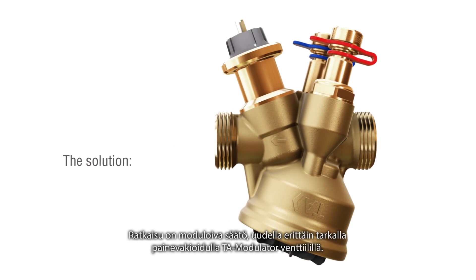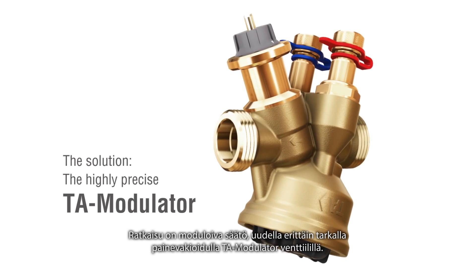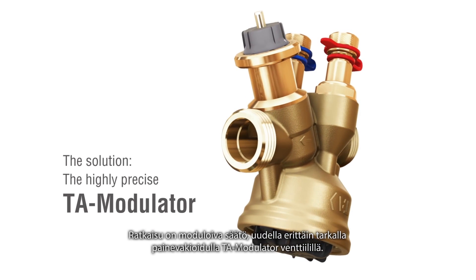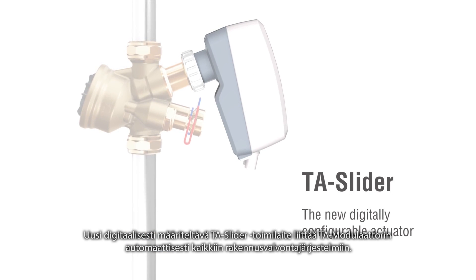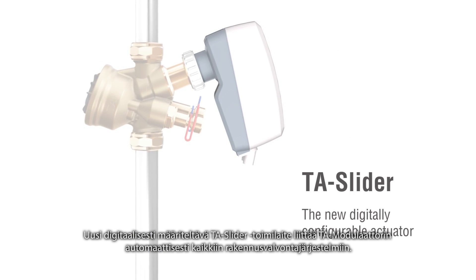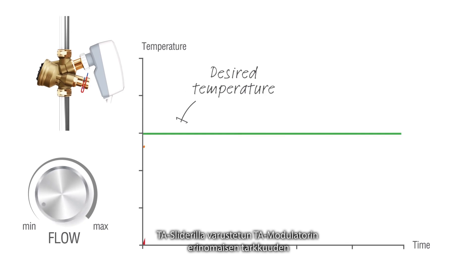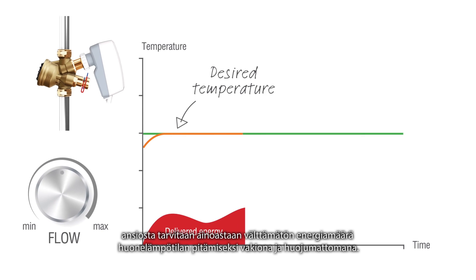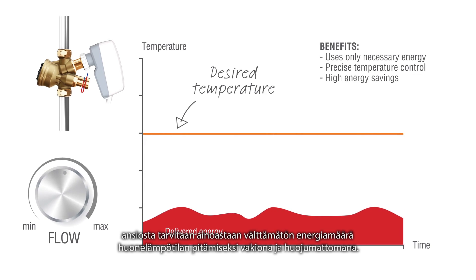The solution is modulating control with the new highly precise pressure-independent control valve TA modulator. The new digitally configurable actuator TA slider connects TA modulator to all building automation systems. Due to the superior accuracy of TA modulator with TA slider, only the necessary amount of energy is delivered to keep the temperature constant without any oscillations.